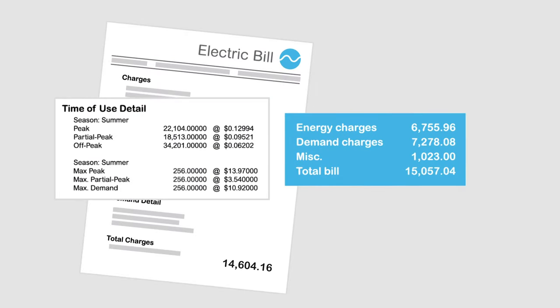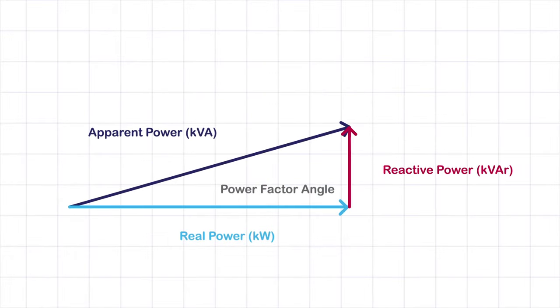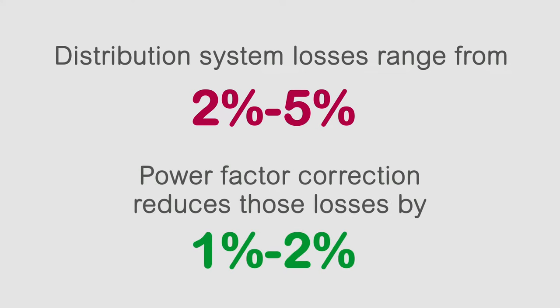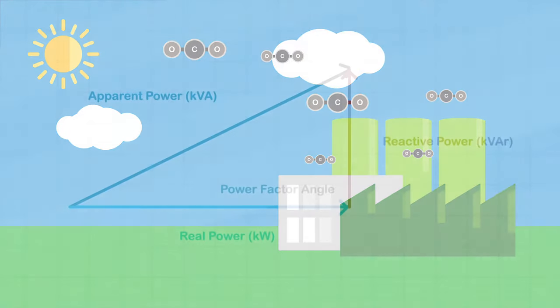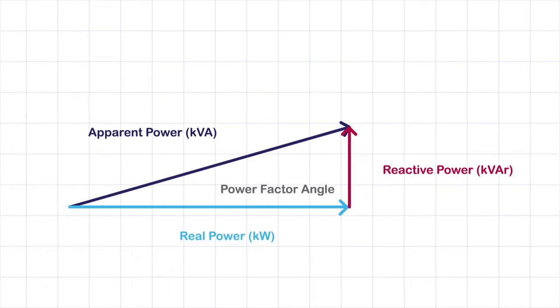It can reduce utility bills by reducing your demand charges which relates to your rate structure. It reduces apparent power therefore reduces loading on your power transformer and distribution network. Reduces I squared R losses. Electrical distribution systems have losses ranging from two percent to five percent. Correcting power factor reduces the losses by one to two percent. Reduces carbon emissions since we reduce the I squared R losses. Improves voltage regulation by correcting the power factor. We reduce the loading on the network therefore reducing the voltage drop across the network impedance.